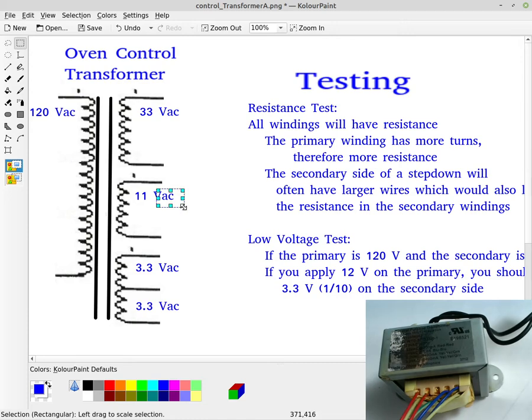And if you're going to have 10 amps on the secondary side, then you're going to need much larger wire to handle that much larger current, and therefore the wire would have larger diameter, which would reduce the resistance also. Now in this particular case, this oven control transformer, we're not going to be drawing anything near 10 amps on the secondary side, so the wiring isn't all that huge, because you gauge your wiring based on the load you're actually going to connect it to.